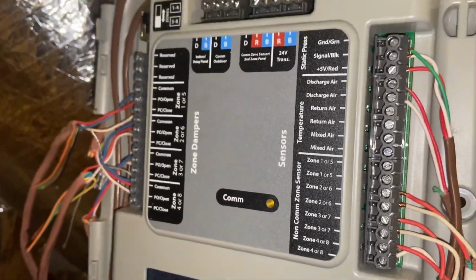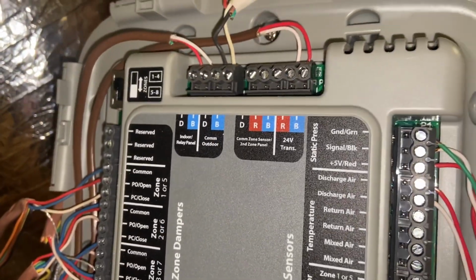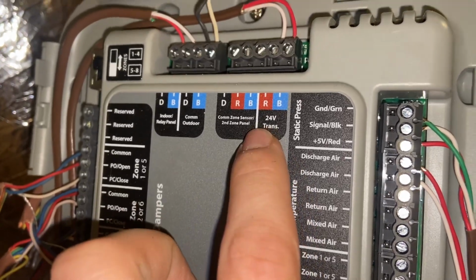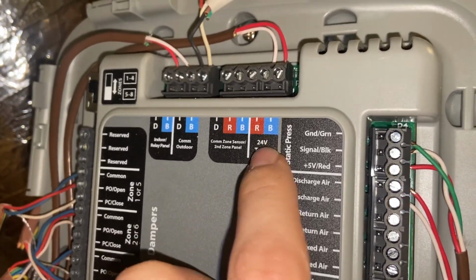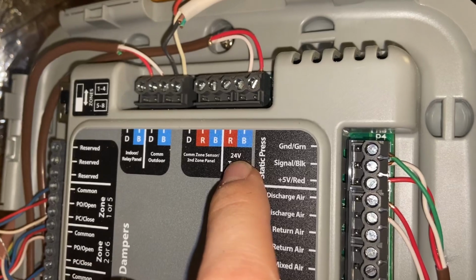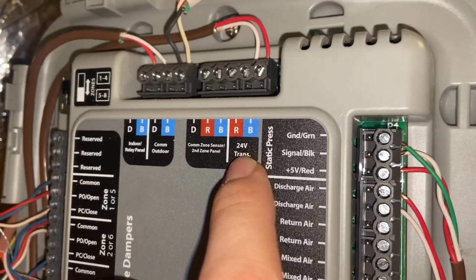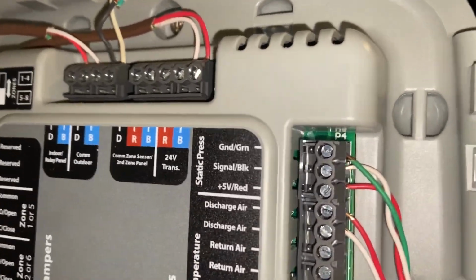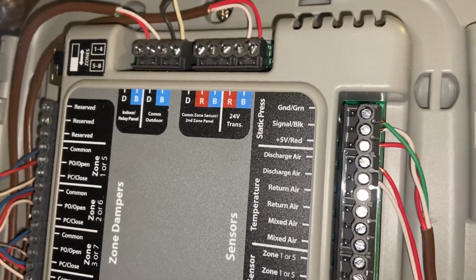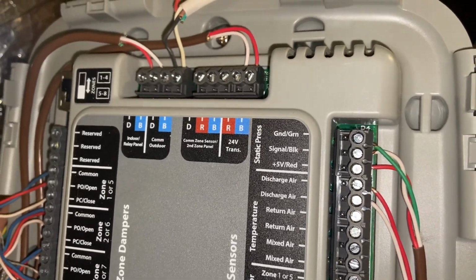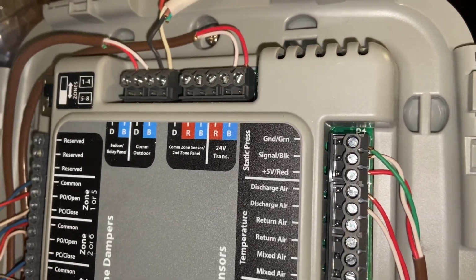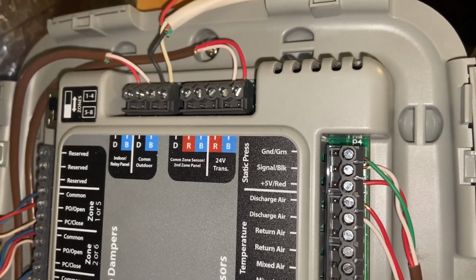So I went and got the multimeter and I was looking around here, and you can see right there, 24 volt trans — okay, that's our power input. I should have 24 volts there and I did not. So 24 volt trans, well that tells me okay, there's a transformer, so probably AC, right? 24 volts AC, powered by a transformer. Follow the wires back.